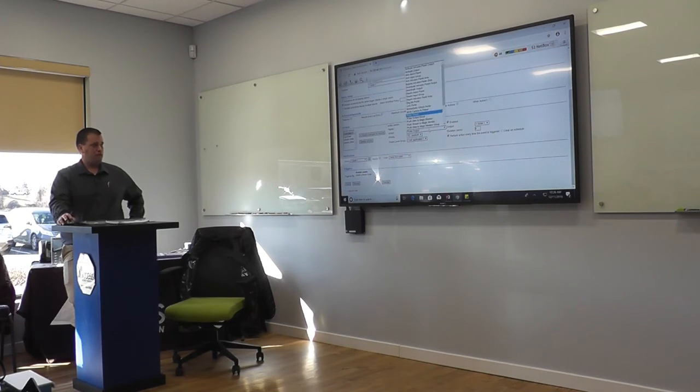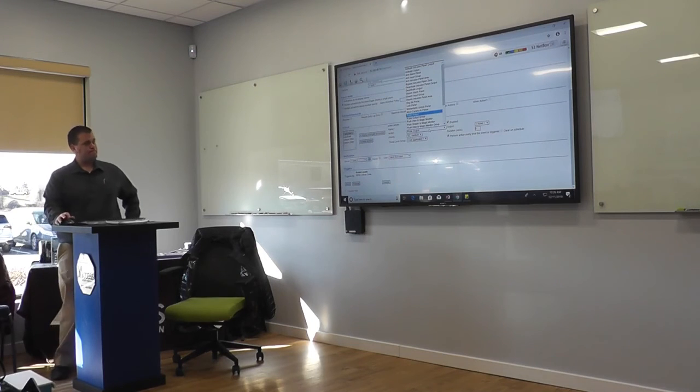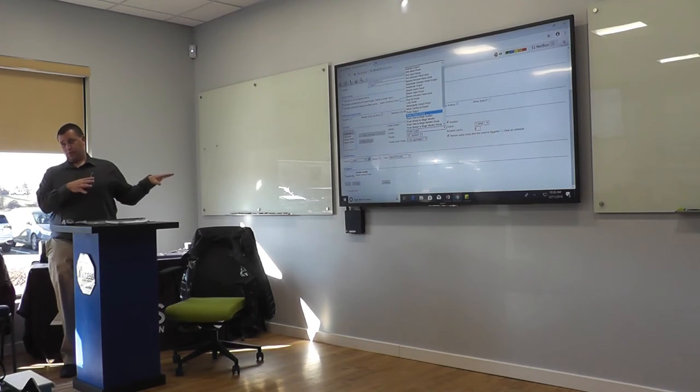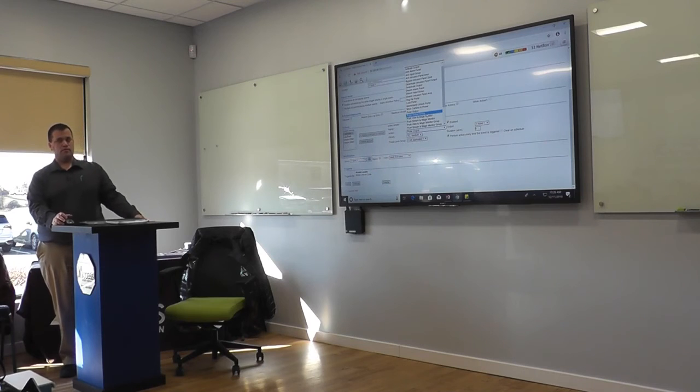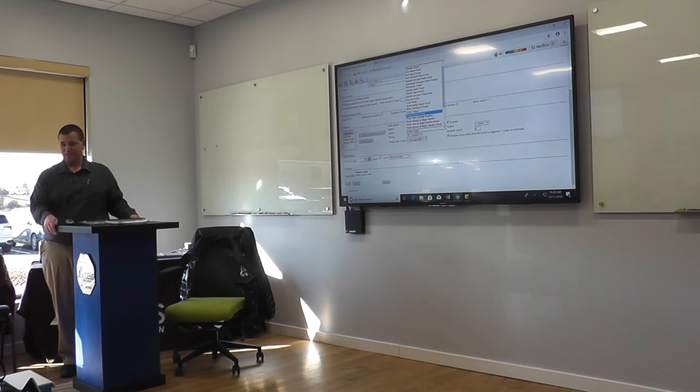Pulse output is kind of like activate output, but it just sends a momentary pulse to the output. And then pulse output group, if you have a group of outputs configured in the system that you want to pulse, you could have it send it to that group. What would be on an output? Sometimes a light or a bell, a sounder, a light or a buzzer, or an alarm. You could put anything electrical pretty much. You can have an output activate or deactivate.